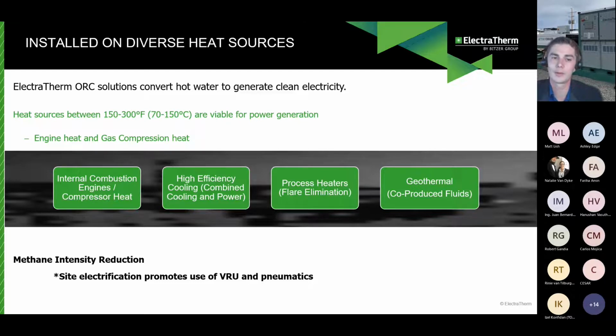We can operate down to even 150-degree Fahrenheit heat sources. So that's where we function as high efficiency cooling, but also process heaters. So if a site flares a lot of gas, we can eliminate the need to operate that flare by using a process heater and an ORC system. And then geothermal resources. So a lot of oil and gas sites have some form of geothermal resources, some even approaching 200 Fahrenheit, that can be very viable and reasonable for power production from that heat.